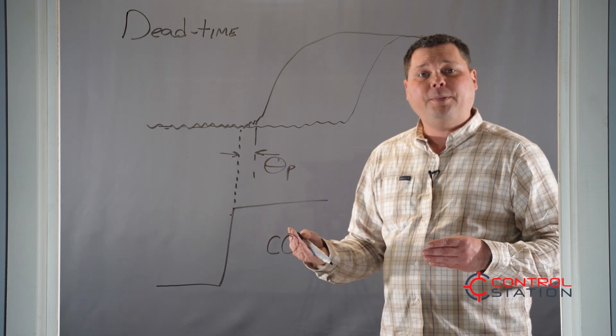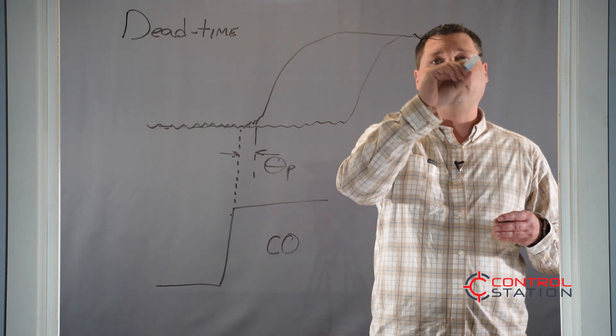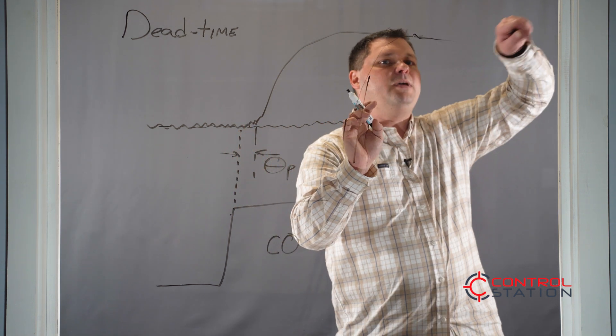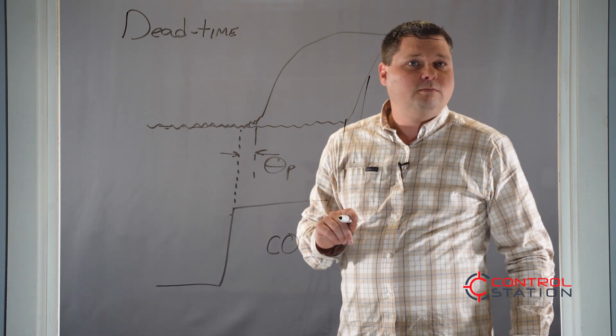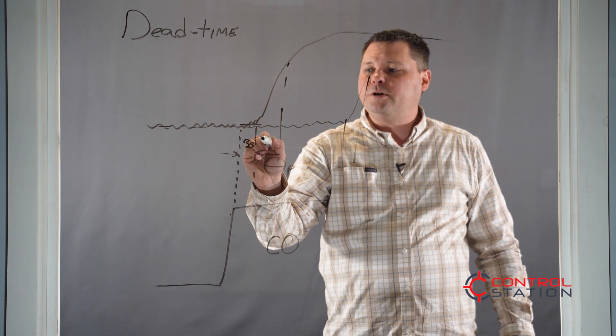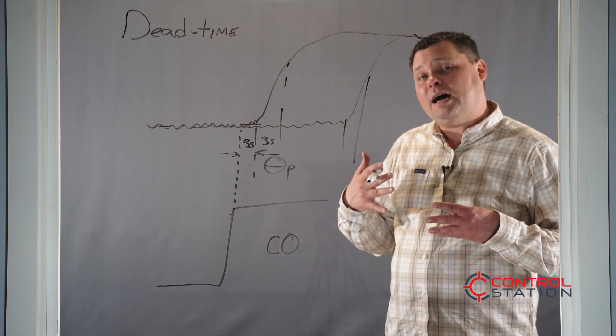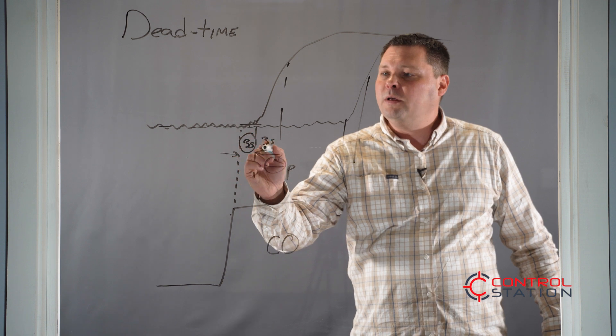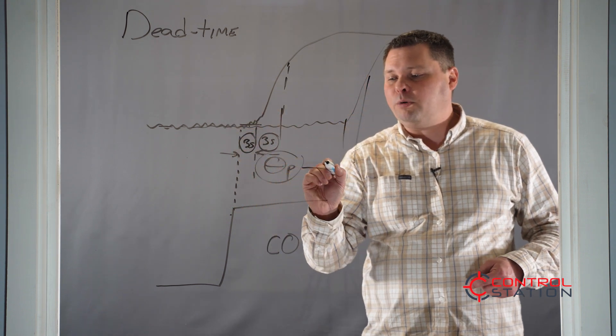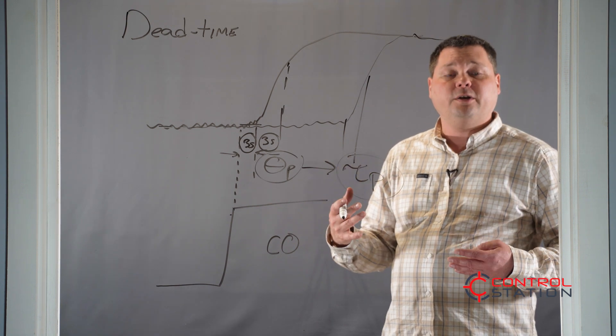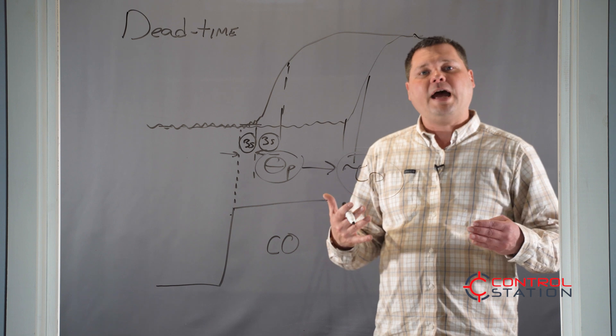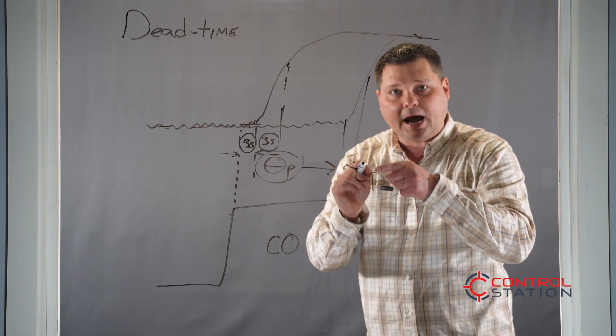They make a change and nothing happens. This delay is really difficult for the PID controller to deal with in times where the time constant is quick. If it takes five seconds for this to respond but 50 minutes for the process to continue its response, that's not a big deal. But if this dead time is, say, three seconds, and my process time constant is also three seconds, that's actually a significant dead time relative to the time constant of the system. As the dead time starts to approach that time constant, you start to get difficult control scenarios. It becomes difficult to control the process quickly — you become what is known as a dead time dominant system. The time factor in the process is limited by the dead time and not the time constant.